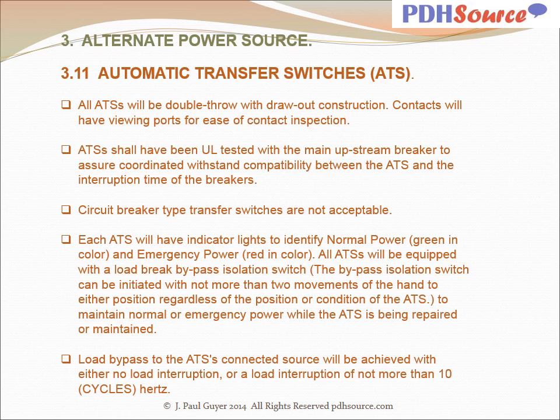With regard to the automatic transfer switches, all ATSs will be double throw with draw-out construction. Contacts will have viewing ports for ease of contact inspection. ATSs shall have been Underwriters Laboratories tested with the main upstream breaker to assure coordinated withstand compatibility between the ATS and the interruption time of the breakers. Circuit breaker type transfer switches are not acceptable. Each ATS will have indicator lights to identify normal power, green in color, and emergency power, red in color.